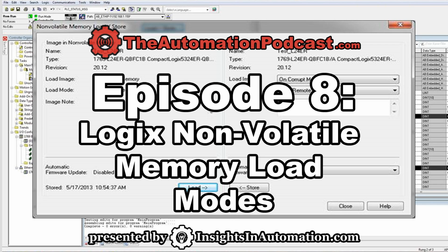To do that, inside of RSLogix 5000, you're going to go to controller properties. Now, there's 2 different ways to get there. You can either right-click on the controller organizer and select controller properties, or underneath that little graphic of the key switch on the toolbar, there's a little button there with a PLC on it. Click that, and that'll bring you to controller properties as well. So inside of controller properties is the tab labeled non-volatile memory.